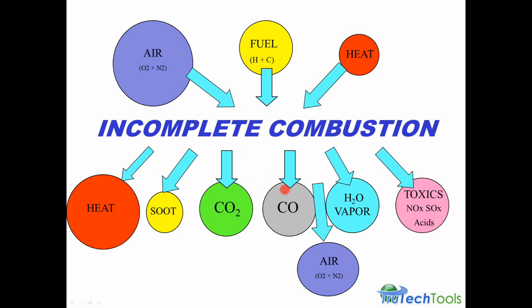That means there wasn't enough oxygen around where the fuel was being broken down and combusted and oxidized to go all the way to CO2, so CO is formed. As we'll be talking about later, CO is formed when there's an incorrect mixture of fuel and air, usually not enough air for the amount of fuel that's being combusted. You still get the CO2, you still get water vapor, and you can also get toxics. These toxic effluent products can be nitric oxides, or NOx, or SOx, sulfur dioxides. The nitric oxides can come from nitrogen that may be in the fuel or the air, and the sulfur dioxide can come from sulfur, which is usually in the fuel, but to a lesser extent lately with the low sulfur fuels that are burning nowadays.